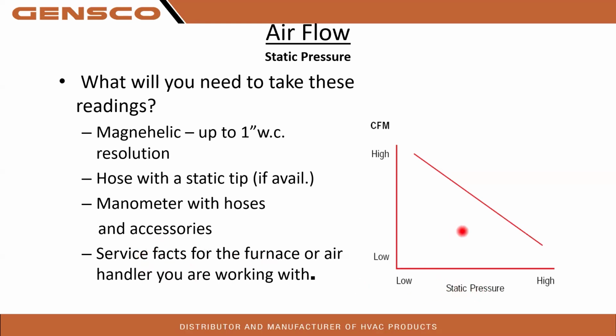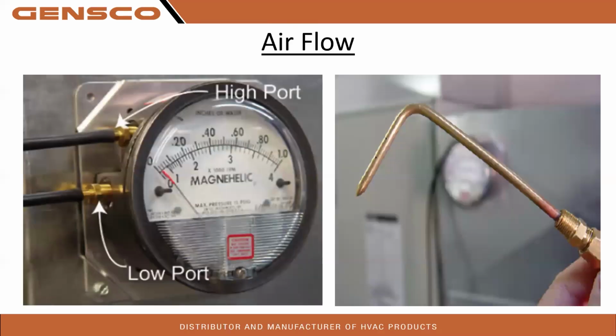Here's higher static pressure, we have lower CFM. Lower static pressure will increase CFM. These are labeled on the side as positive, negative. So you'll have negative going to your low port, which will be the negative return air pressure. The high would be your supply side.